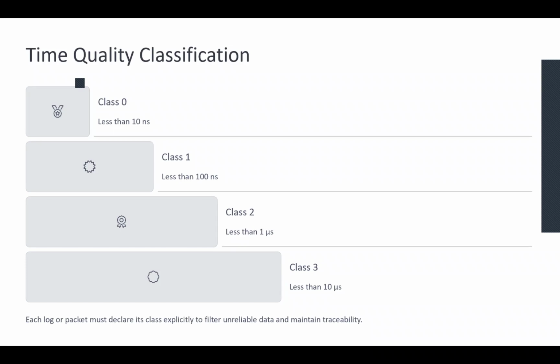Accepting or rejecting data based on the required accuracy is another aspect of why these classes are important. Only class 1 and above are accepted for fast frequency response. If we have a highly sensitive system that needs class 1 quality of time, and it gets data tagged as class 2, it should reject it. Having an explicit time quality classification makes sure of traceability and legal accountability.